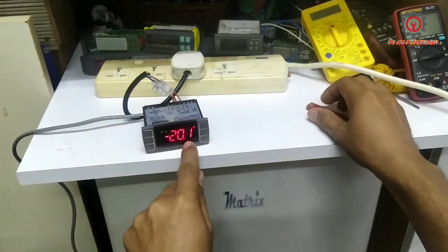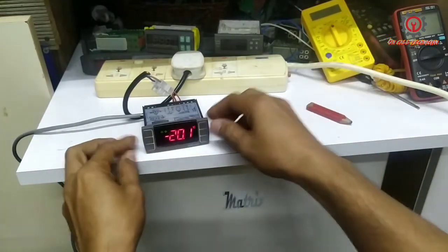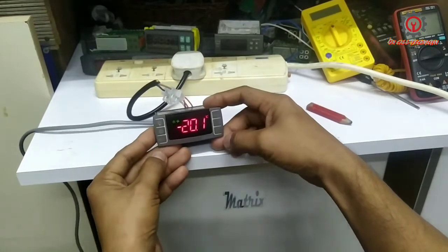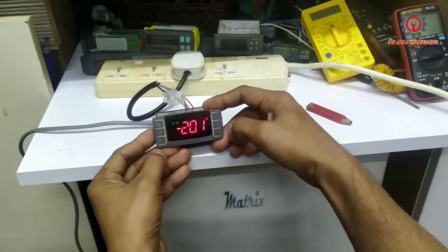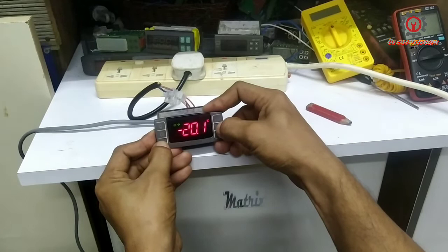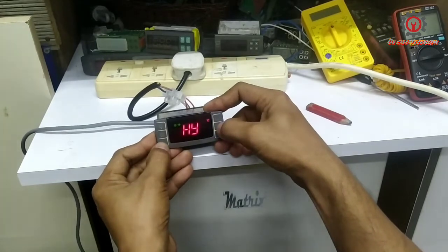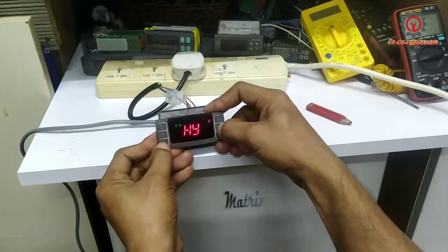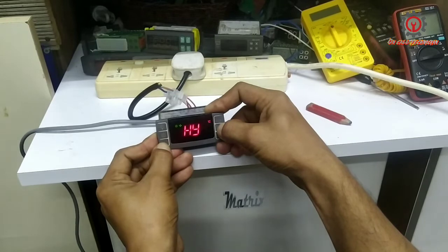I'm going to access that. It's not showing the real temperature. To enter the parameter, press the SET button and arrow down button for 3 seconds, and another SET and arrow down button for 7 seconds to enter the hidden parameter. We're going to access the DAD.